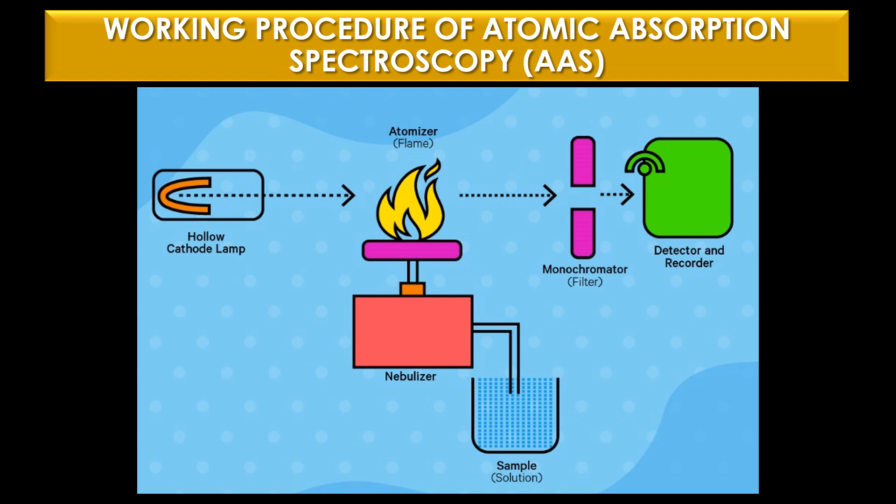Working procedure of atomic absorption spectroscopy: The sample, either liquid or solid, is atomized in a flame or a graphite furnace. The free atoms are then exposed to light — typically produced by a hollow cathode lamp — and undergo electronic transitions from the ground state to excited electronic states. The light emitted by the lamp corresponds directly to the wavelength absorbed by the atomized sample. A monochromator is placed between the sample and the detector to reduce background interference, and the detector then measures the intensity of the light beam and converts it to absorption data.